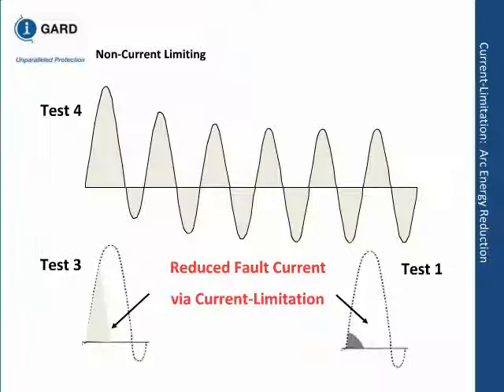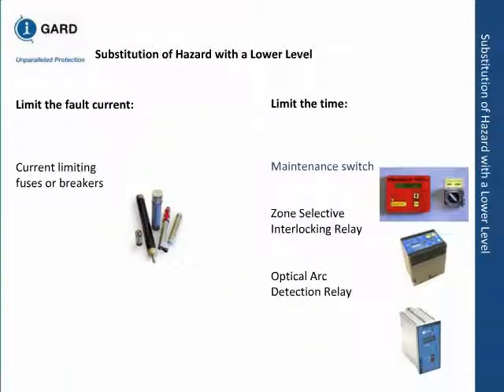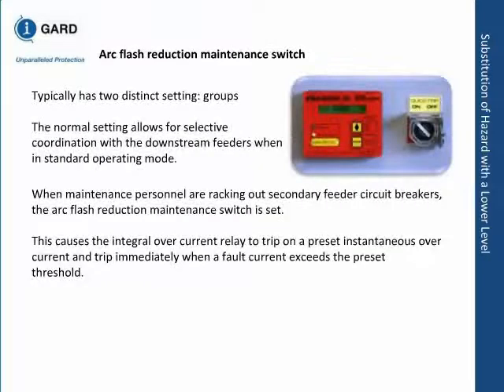Okay. Other technology: maintenance switches, zone selective interlocking, and optical arc detection. What is a maintenance switch? When you have two protective devices in series, normally you cannot use instantaneous. Two instantaneous cannot be coordinated. So you put the upstream device on what we call short time. Give it a little more time to clear the downstream fault. The convenience of a little more time for clearing the downstream fault also causes us to have excessive arc flash. It takes a long time.